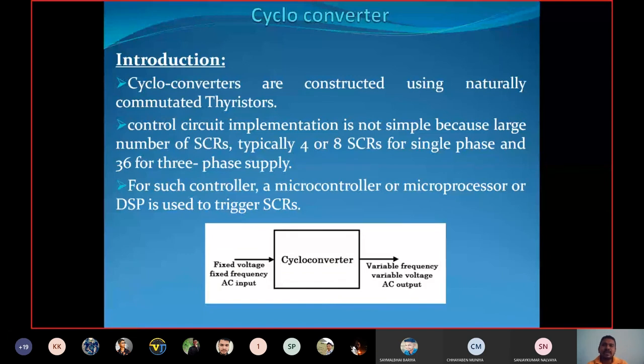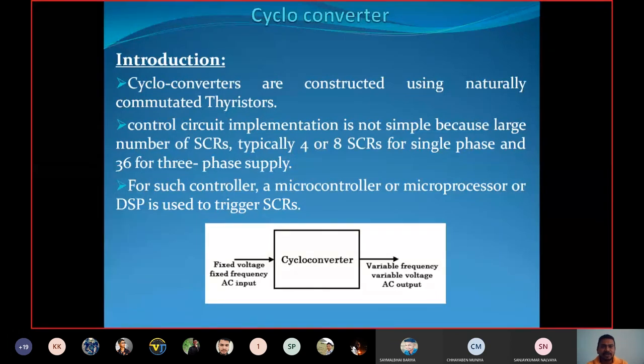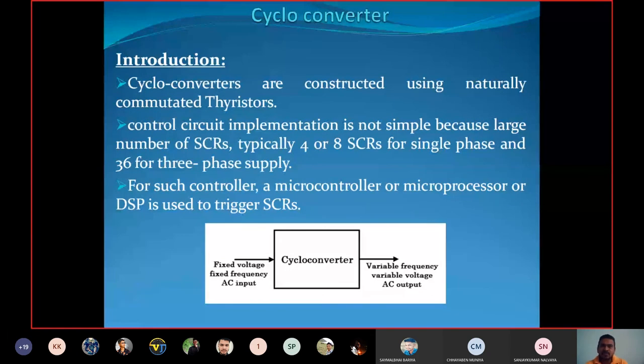Control circuit implementation is not simple because a large number of SCRs are required — typically 4 or 8 SCRs for single phase and 36 for 3-phase supplies. As the number of SCRs increases, the control circuit implementation becomes very complex. For such a controller, a microcontroller, microprocessor, or DSP is used to trigger the SCRs.